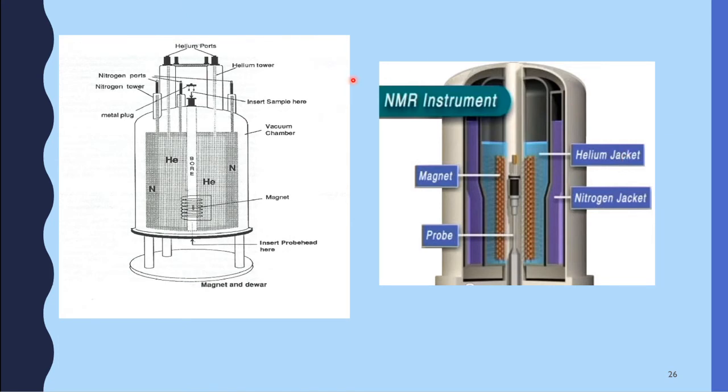though you may have a more sophisticated machine, the concept is still the same, and you still have this superconducting magnet being protected by the liquid nitrogen, and on top of that being protected by the liquid helium.